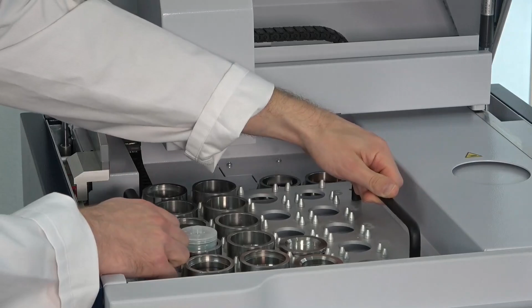Now, especially if the system is used for multiple purposes, for instance, analyzing the liquids as well as the dried hydroxide precursors, we built in a so-called liquid cup detection, which is essentially a fail-safe for the system. So even if the operator starts the wrong analysis, the system itself will recognize a liquid cup and not run the wrong type of analysis on a liquid. So if this happens, instead of loading the sample, the system will just continue with the next sample, giving a warning so that the operator can later on correct his mistake without interfering with the whole analysis sequence.